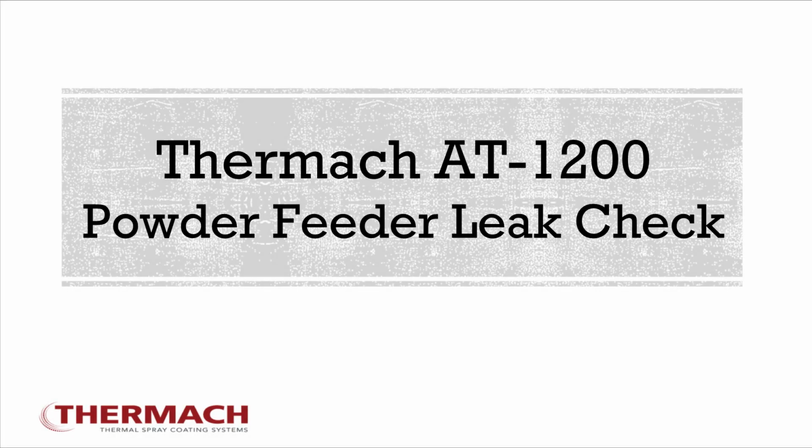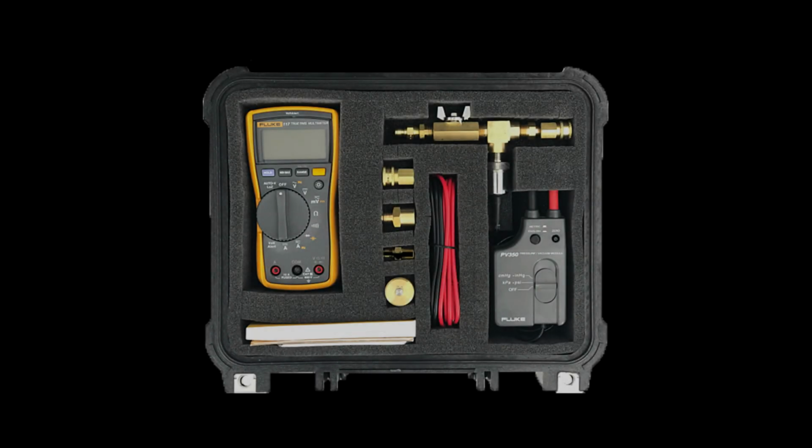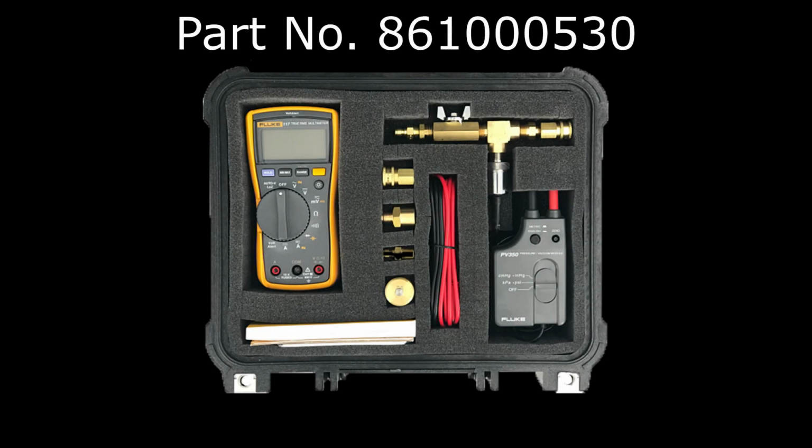Welcome to this training video, which will demonstrate how to check your AT-1200 powder feeder for leaks after a cleaning. Required to perform this operation is a pressure test kit available from Thermach. Shown here, it includes a multimeter, pressure transducer, and various plugs, connectors, and cables.